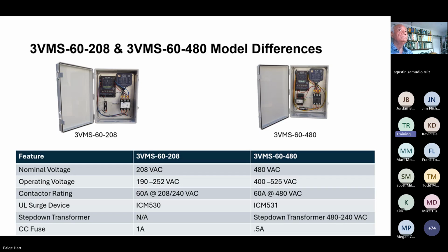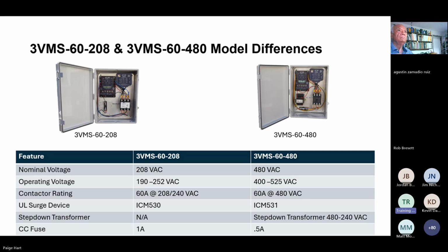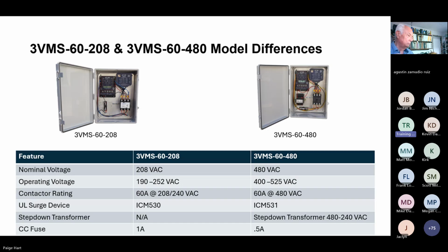Contactor rating, amperage stays the same, but we have to step down the voltage for the 480 volt unit because the contactor's coils are both 240 volts. And we show that a little bit further down here, but it's the UL listed surge device on the 208 version, of course, the 530 rated for 208, 240. And then for the 480 volt version, we have the 531 in there. Again, I mentioned the step down transformer, not necessary in the 208 version, but necessary in the 480 volt version to step down that voltage so we can use the same contactor.